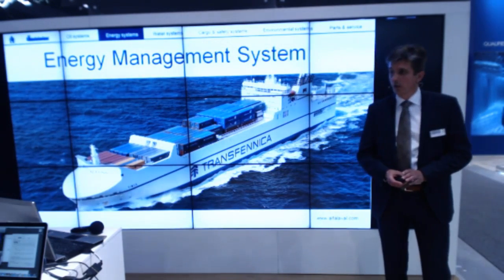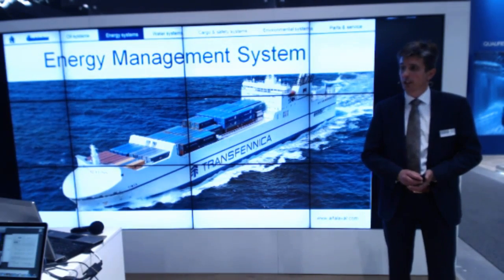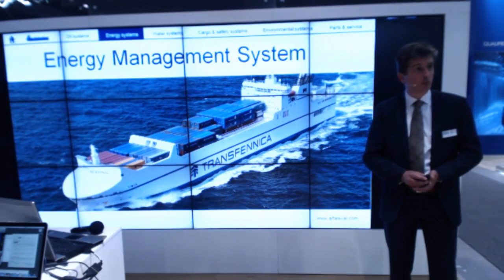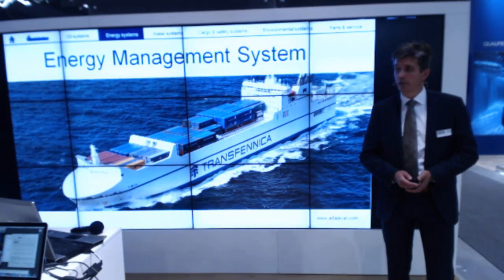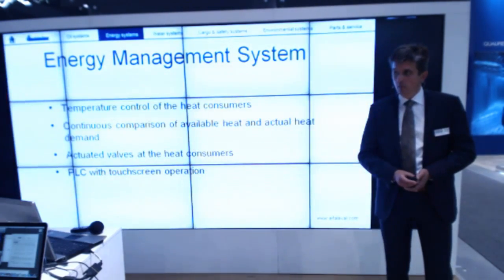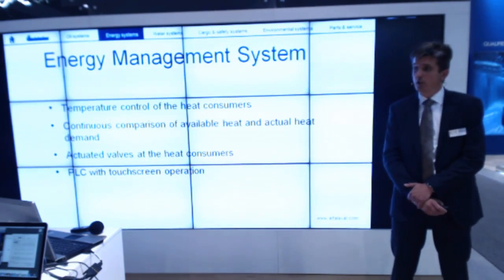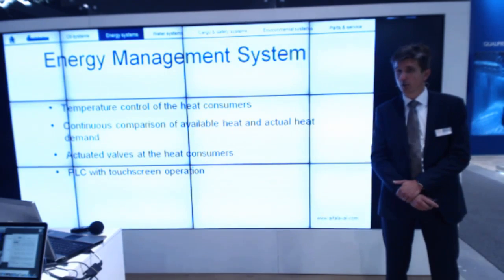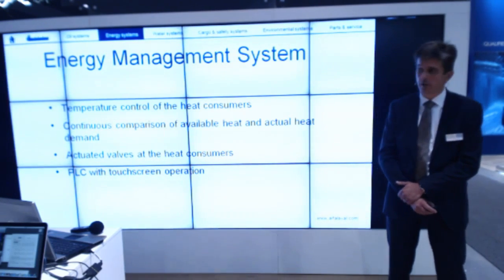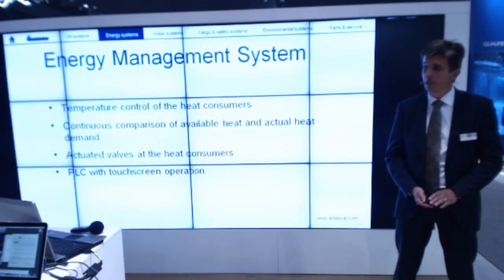In addition to a standard system where normally all the heat consumers are controlled by manual operated valves, we have an additional system called Energy Management System, or EMS, where each and every heat consumer on board can be controlled from the control panel instead of manually. The energy management system is a temperature control system for the heat consumers and makes a continuous comparison between the available heat from the heat sources and the actual heat demand from the various consumers. This is done by actuated valves at the heat consumers and by means of a PLC built into the control panel with a touchscreen for operation by the crew.